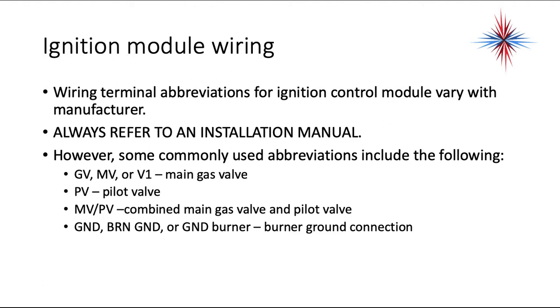Wiring terminal abbreviations for the ignition control module vary with manufacturers. Always refer to the installation manual. However, some commonly used abbreviations for the wiring include the following. GV, MV, or V1 is the main gas valve. PV is the pilot valve. MV/PV is the combined main gas valve and pilot valve. GND, burner ground, or ground burner is the burner ground connection, which is extremely important.